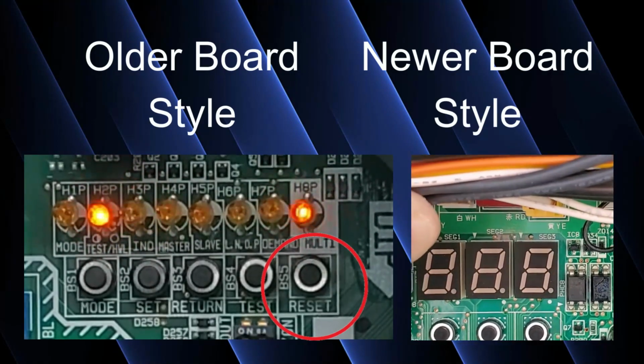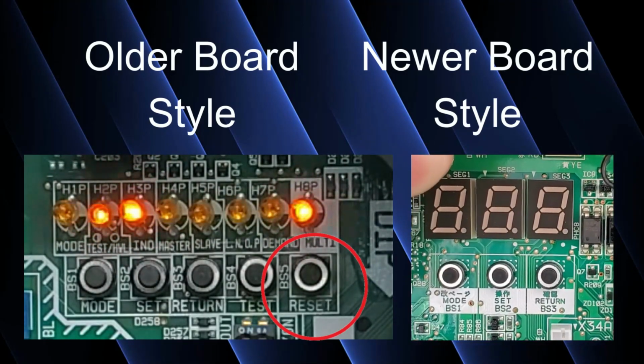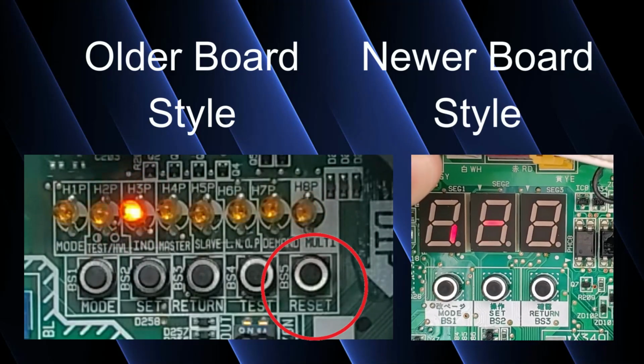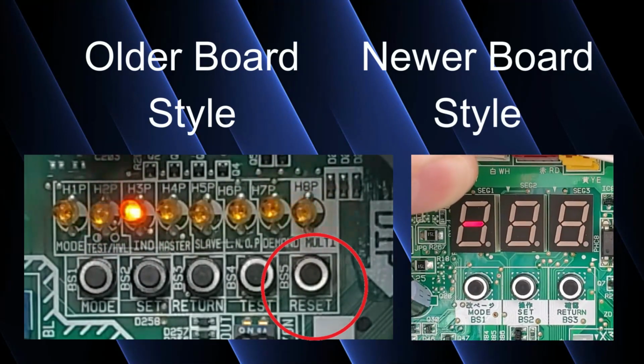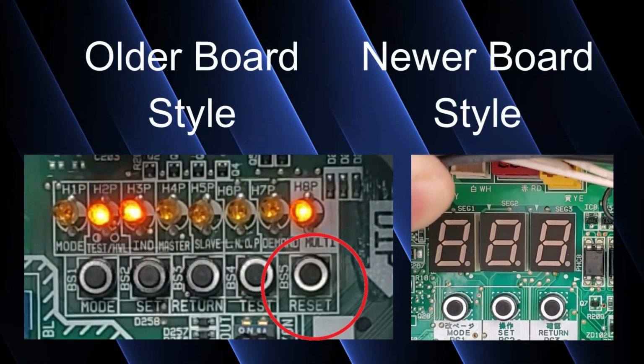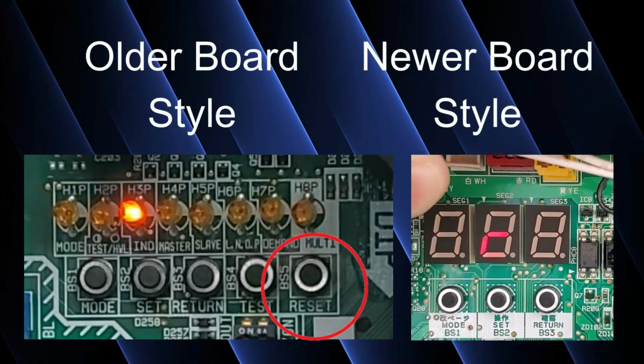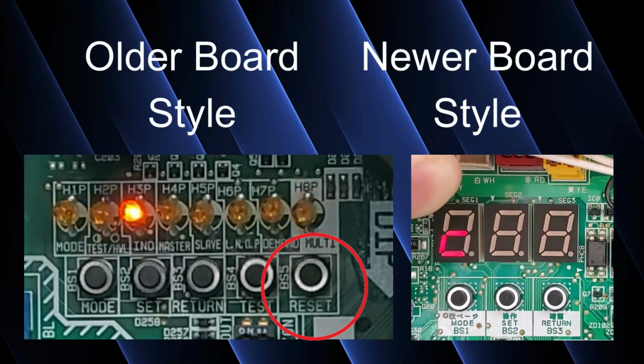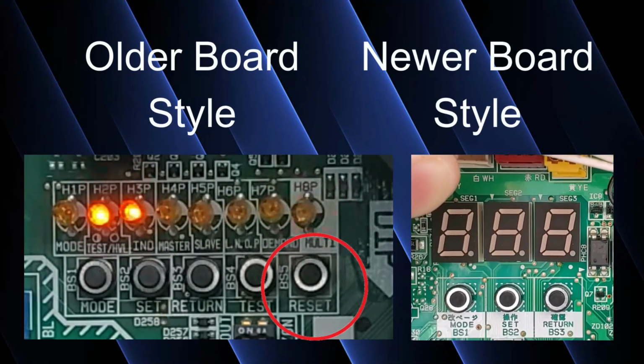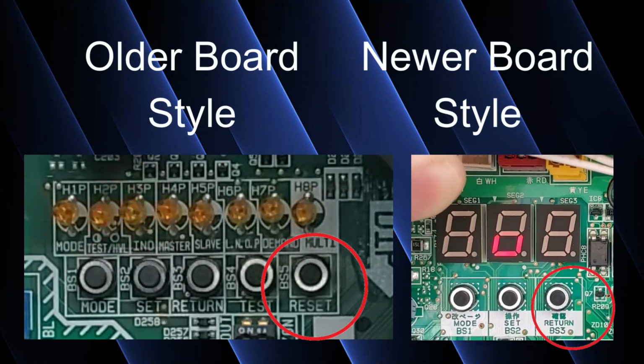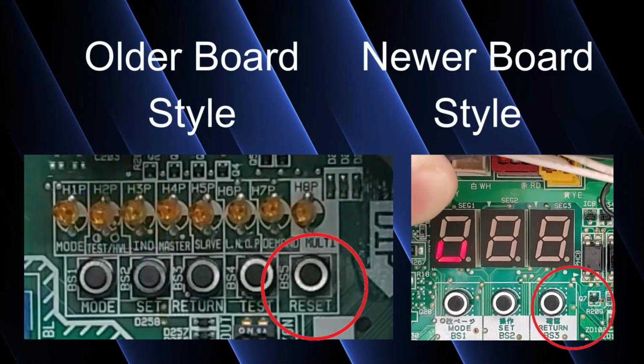Now on the newer boards, VRV4 generation and newer, the one that has the digital display that just pops to you, you only have 3 buttons, you don't have a reset button. When you apply power to the outdoor unit, and you see 3 little circles flashing, that's the initialization process has started. You press and hold the return button for 20 seconds and then let go. In either case, whichever board you have, after you've pressed and held their respective buttons for 20 seconds and then let go, the screen doesn't change.